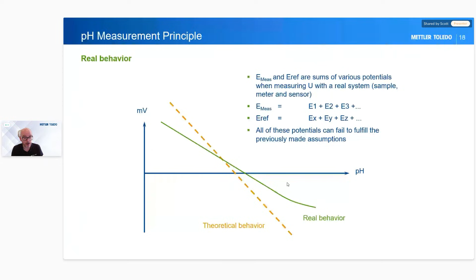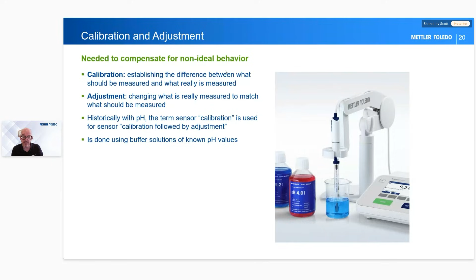So when we're doing calibration, we normally say we want to calibrate the pH meter. In reality, we're not just calibrating the pH meter, we're also adjusting that curve so that we're adjusting for the real behavior that's going on in our labs. The calibration is, we know what our calibrants are, we know what our pH buffers are going to be because it's written on the bottle. And the pH meter, in the case of Mettler Toledo, has them pre-programmed into the meter. So when we come to use our buffers, it can adjust to the real behavior that's happening in our system between the electrode, the wires, the buffers, and the meter itself. So when we do a calibration, we're doing a calibration followed by adjustment, even though we just say we're calibrating the meter. But in reality, we're making that adjustment too.